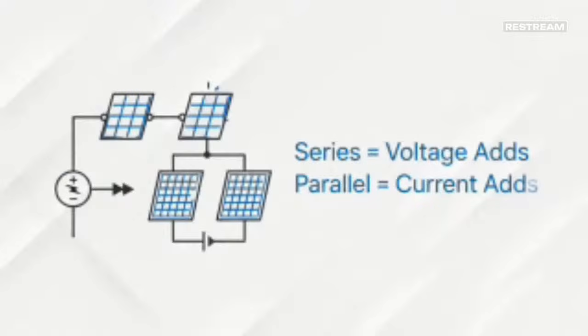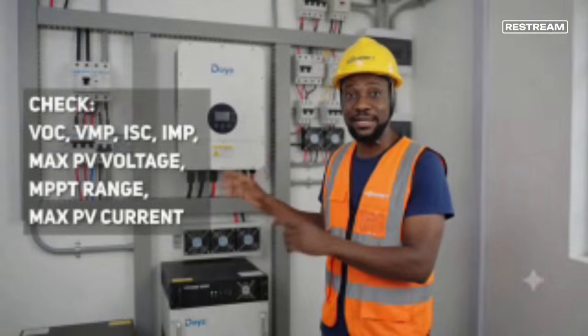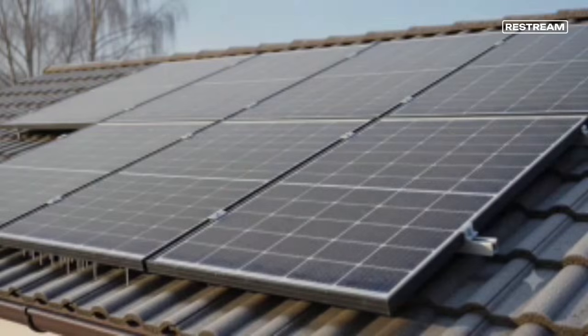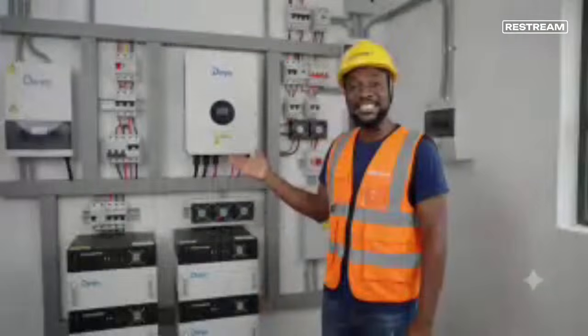Configure the solar array. Design is extremely important. Stay within inverter limits. Check voltage under coldest conditions. Use professional system design. Now we come to DC protect.